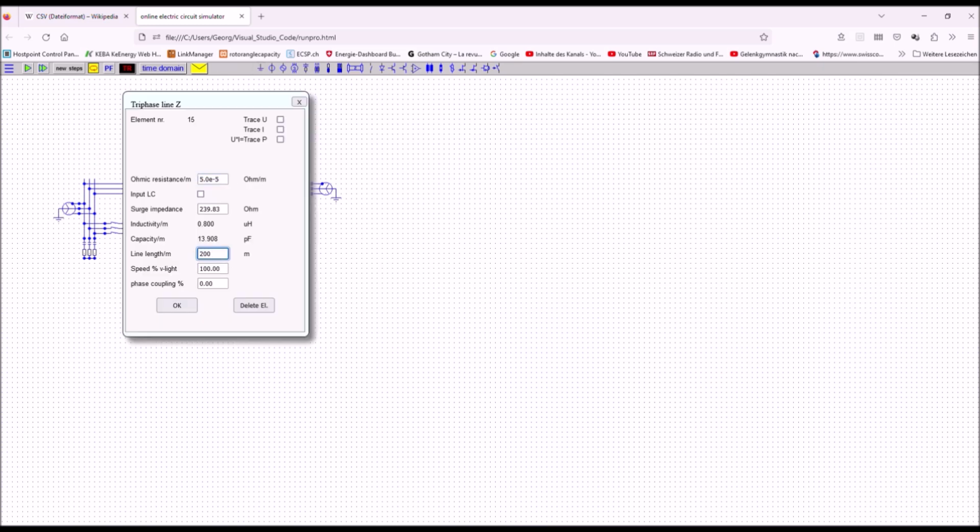On the left side, we build a substation connecting a 300 MVA generator with integrated transient features to two parallel transmission lines. At the midpoint of one of the lines, we build a short circuit, basically a switch. This line is equipped with breakers at both ends. On the right side, we build another source, an infinite bus connected by a longer line. And we also connect the heavy load.